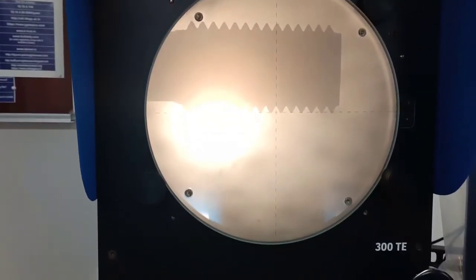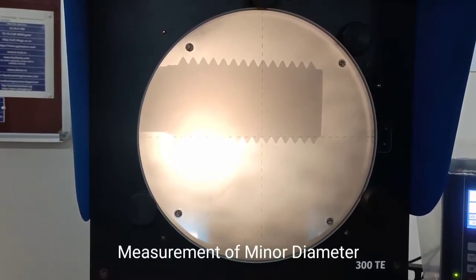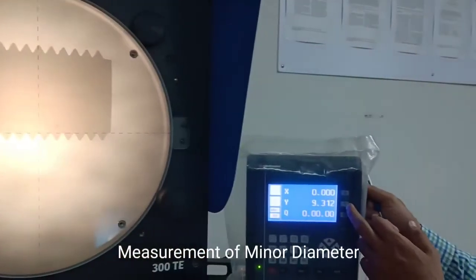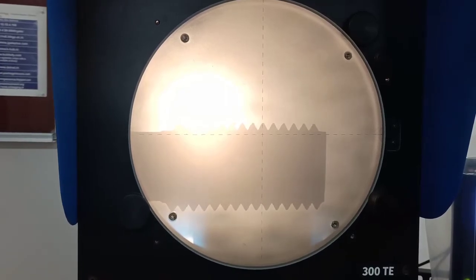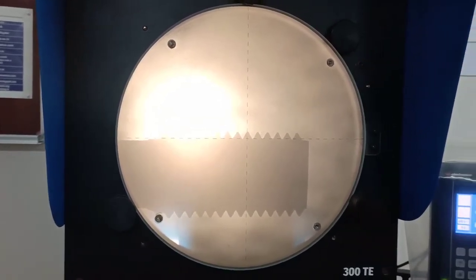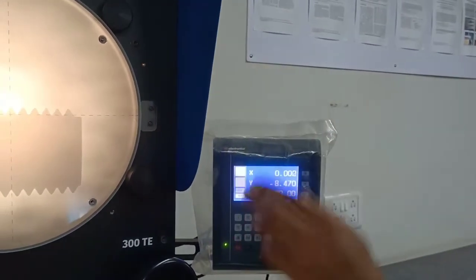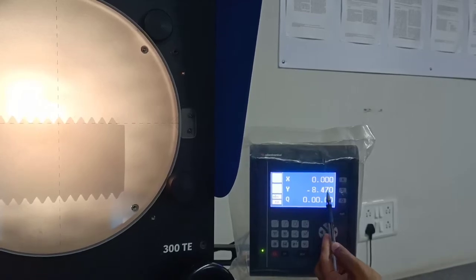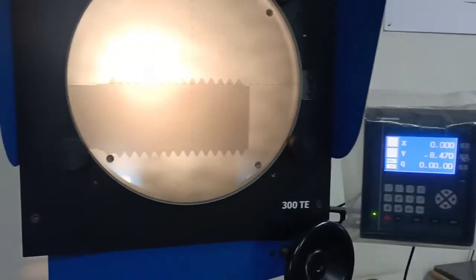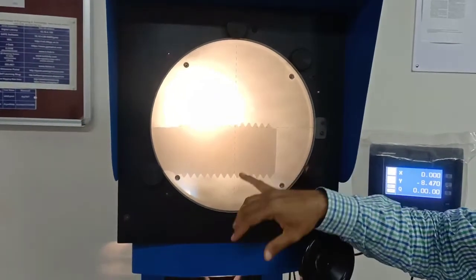Similarly, to check minor diameter, I will set all the root points in touch with the reference line, then set Y to zero. Then I will again move this to all root points on the upper side. It is giving me a reading of 8.470 — it shows minus because we moved the scale in that direction, so if we neglect the negative sign, the minor diameter is 8.470mm. This is how we can use the profile projector to check pitch, major diameter, and minor diameter of a thread.